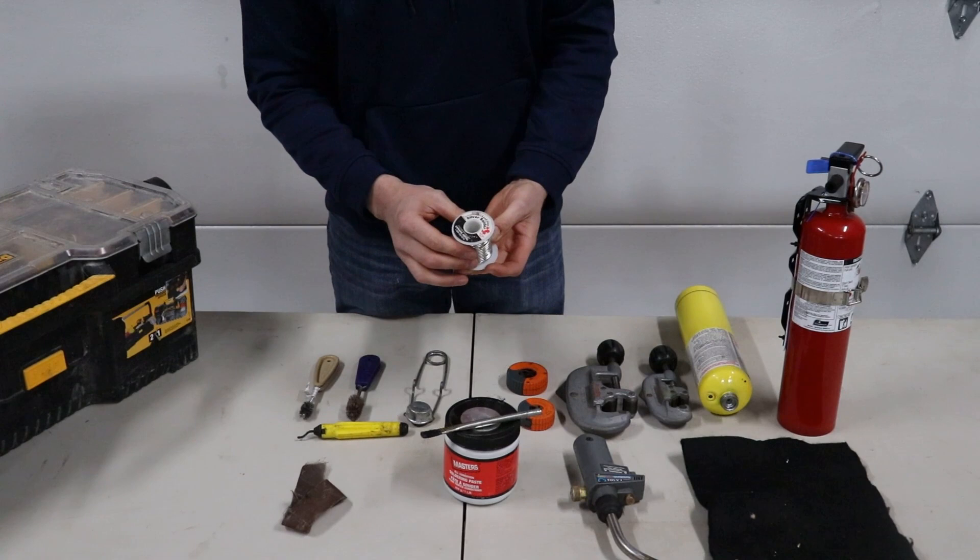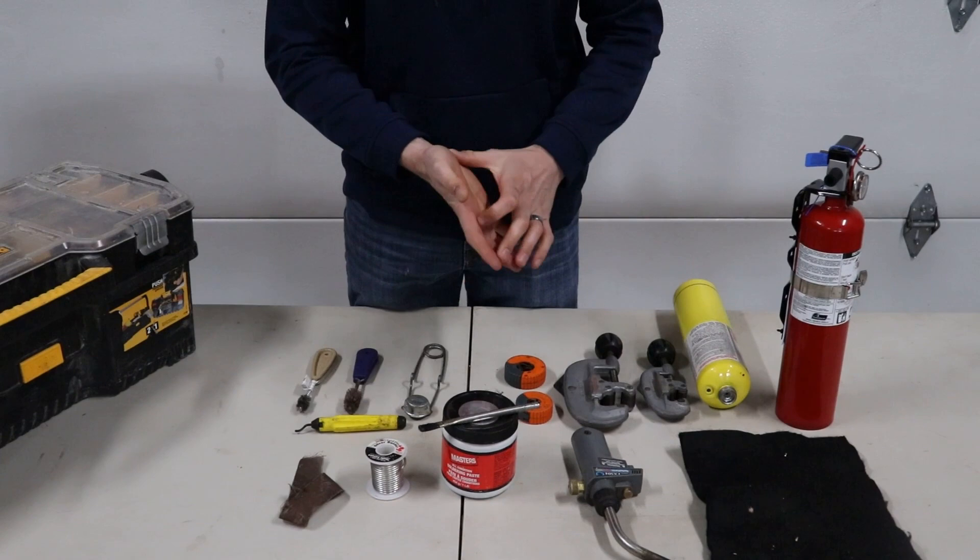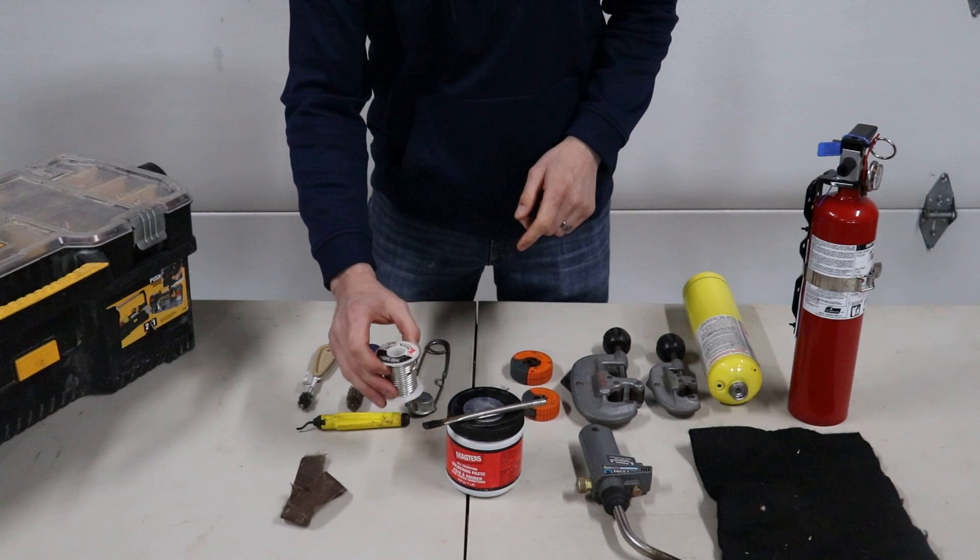We've got the solder. This is 95-5 solder — it's lead free. I'd say 99% of the time we just use this. You can get 50-50 solder, but you can't buy 50-50 at a Home Depot or anything like that. The 50-50 is more for heating and probably more so for drainage than anything, but we still just use 95-5.